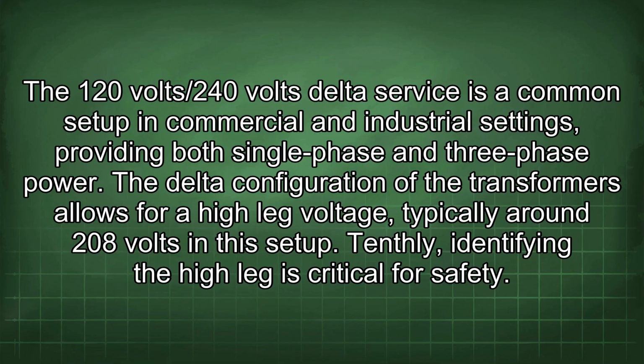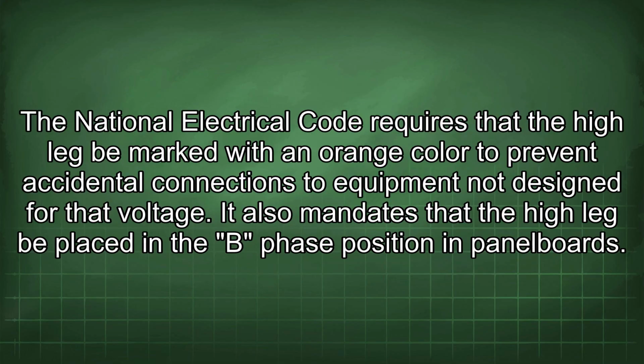Tenthly, identifying the high leg is critical for safety. The National Electrical Code requires that the high leg be marked with an orange color to prevent accidental connections to equipment not designed for that voltage. It also mandates that the high leg be placed in the B-phase position in panel boards.